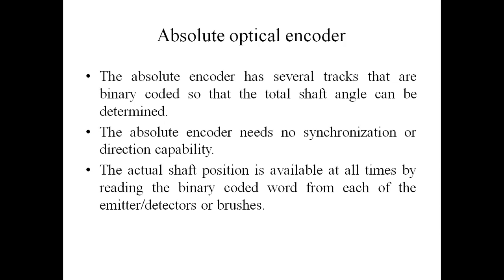When a disk with the pattern rotates, the light passing through the slits is transmitted or blocked according to the pattern. The received light is converted into an electrical current. The detector elements take the form of waves and become a digital signal. This type of encoder outputs the rotation angle in parallel as an absolute value in the encoded code. It has one output for each output code bit, and as the resolution increases, the number of outputs increases. Rotation position detection is accomplished by directly reading the output code.